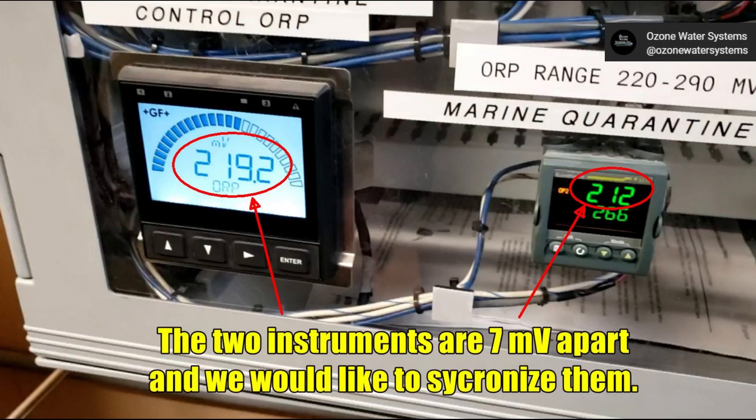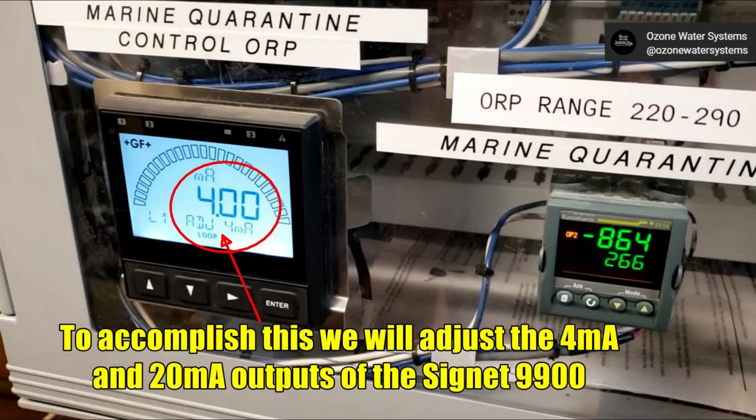In this example, you can see that the Signet and the PID controller readings are 7 millivolts apart and the customer would like them to match. To do this, we need to enter the Loop menu of the Signet 9900 and adjust the 4 milliamp and 20 milliamp outputs.